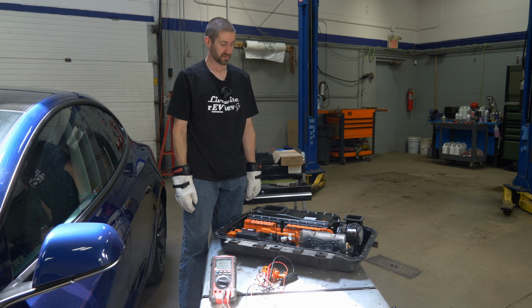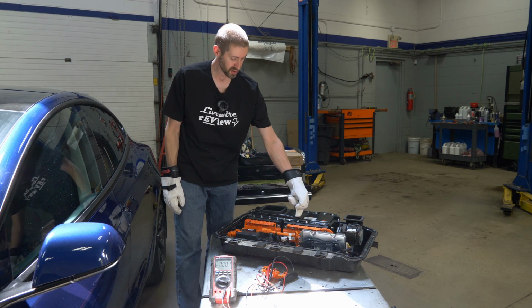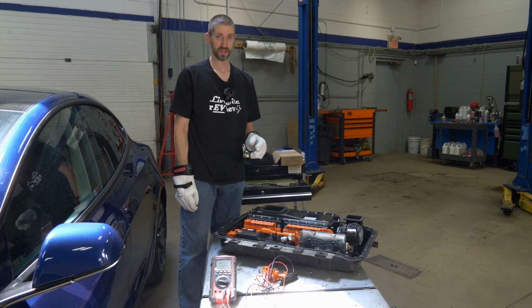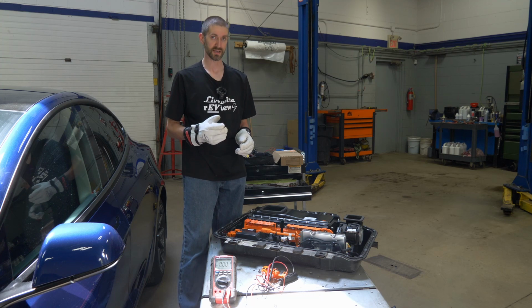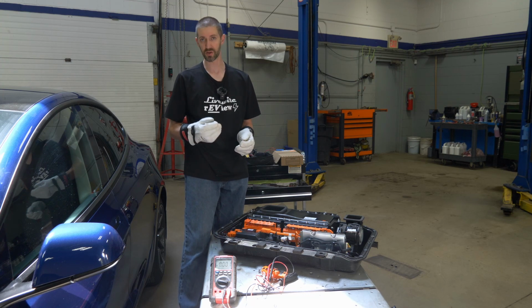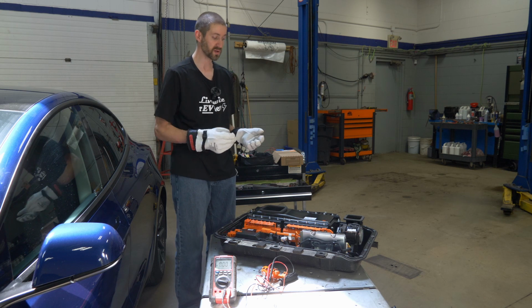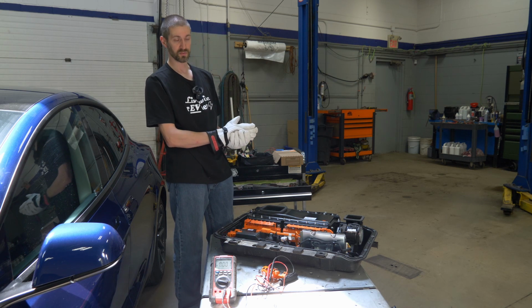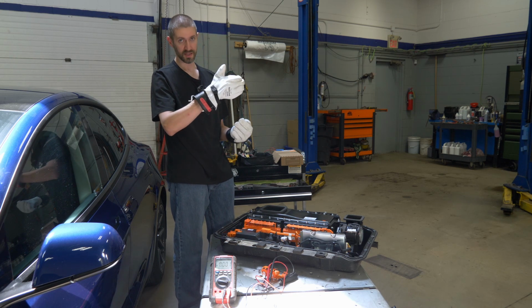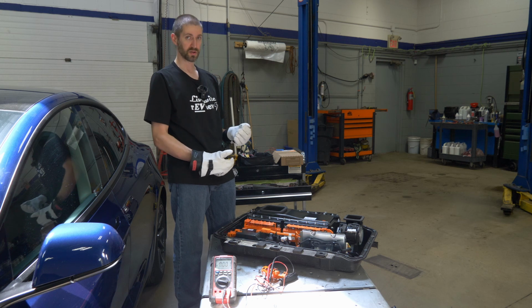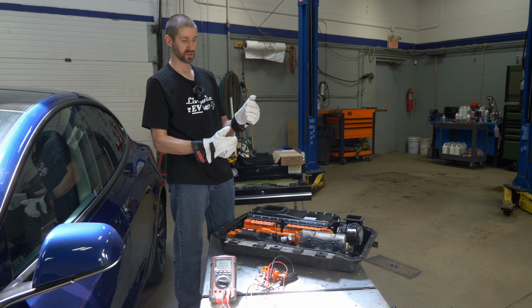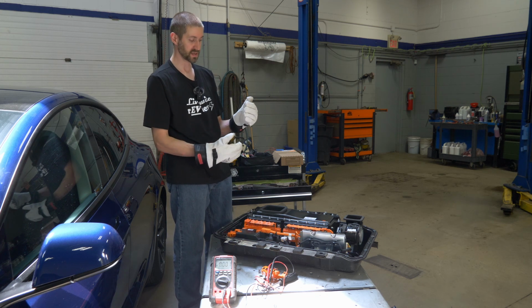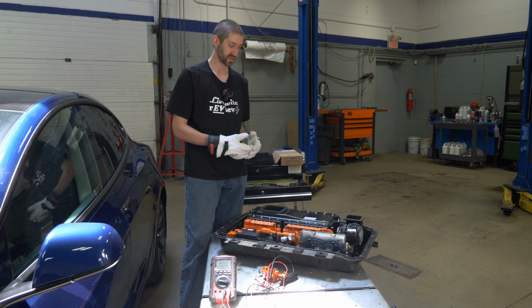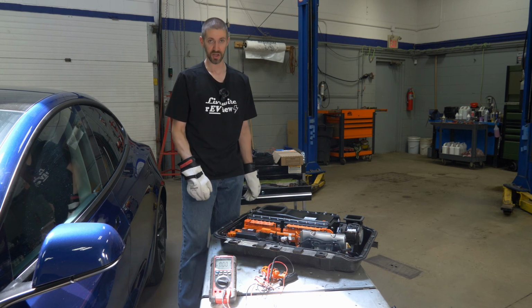So the problem with this battery was very unique. One of the modules, or maybe even two of the modules, had a single cell in them that was not delivering. They would show the voltage, they would charge up, they would do everything they're supposed to do. But as soon as you went to draw a large amount of power through them, one of the cells would drop dramatically. And the computer picked up on this, it noticed the voltage drop from that cell to the rest of the cells, and it said a fault. And unfortunately, we had to remove the battery and change it out.